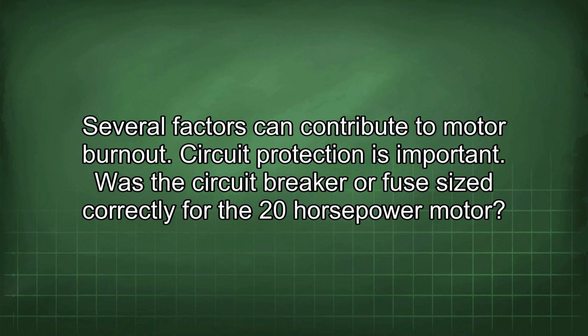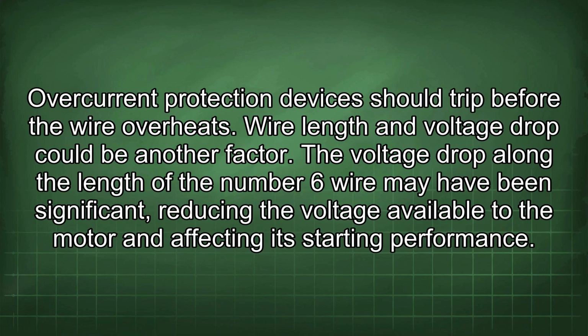Several factors can contribute to motor burnout. Circuit protection is important. Was the circuit breaker or fuse sized correctly for the 20 horsepower motor? Overcurrent protection devices should trip before the wire overheats. Wire length and voltage drop could be another factor.